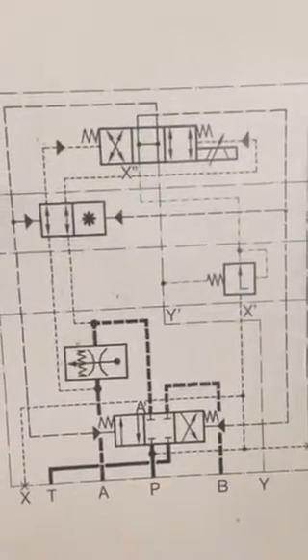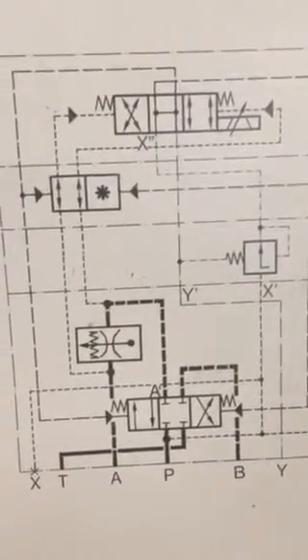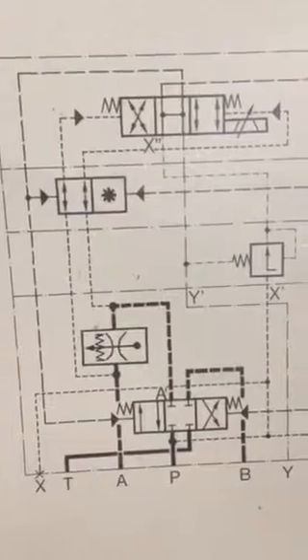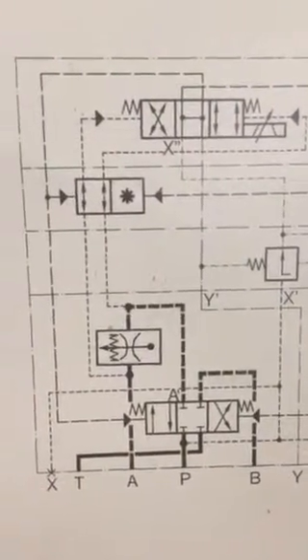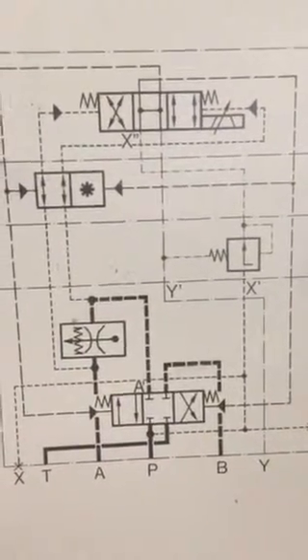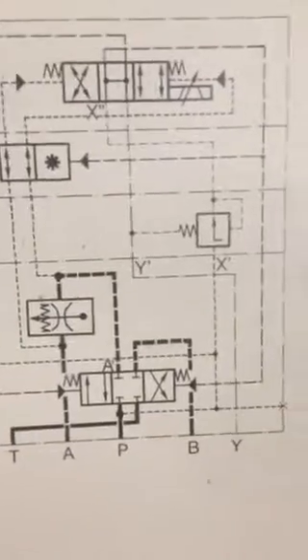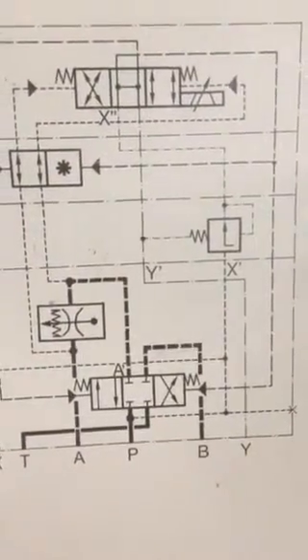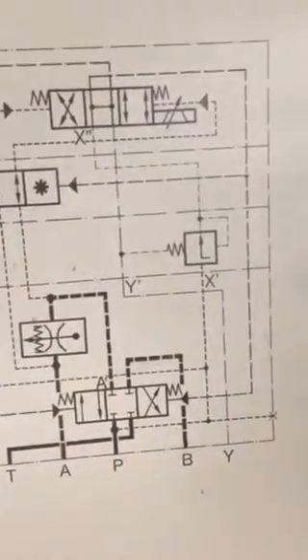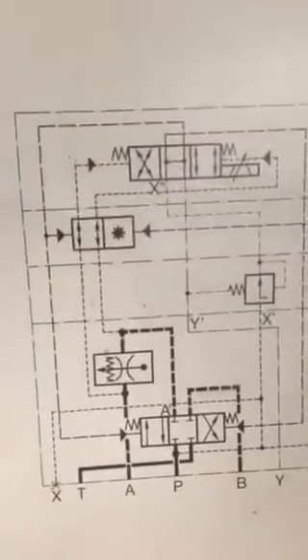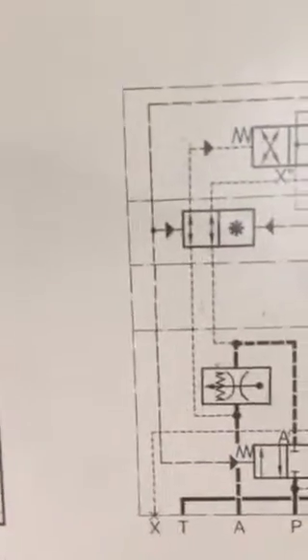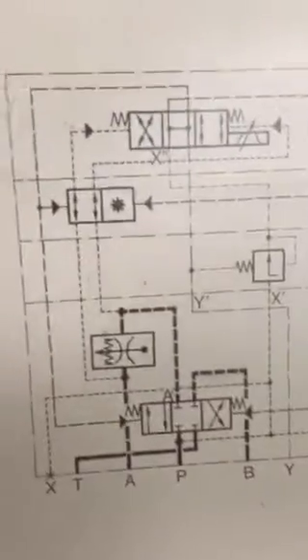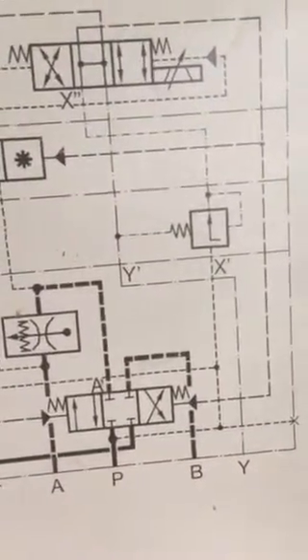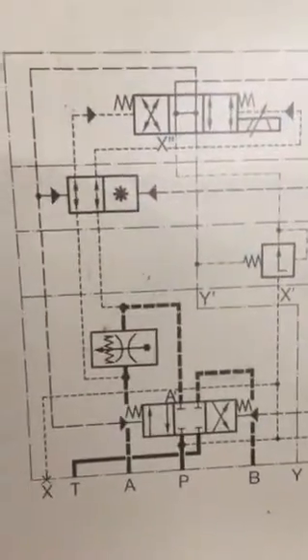And this is the complete schematic diagram of this hydraulic circuit. It shows different valves: pressure reducing valve, pressure reducing adapter valve, and it is also showing directional control valve and electrically modulated directional control valve. So all the parts are in this complete manifold. This is called electrically modulated four-way valve system with internal feedback. Again, electrically modulated four-way valve system with internal feedback.